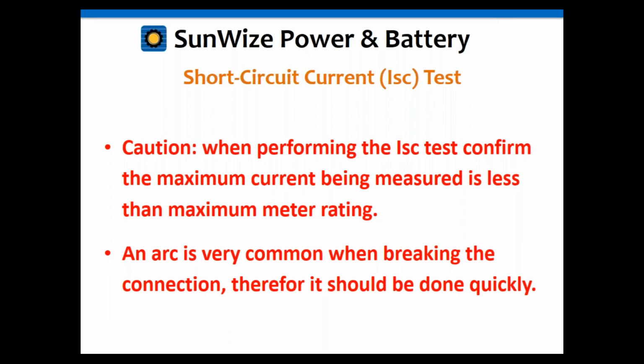And of course, because you have all that current, there's going to be an arc, because you should be doing this in sunlight. If you're trying to get a good measurement, again, you want to do it under the best sunlight conditions. So when you break that connection, you're going to have a decent voltage plus a high current. So there's going to be an arc associated with that. So you want to be very quick about it.